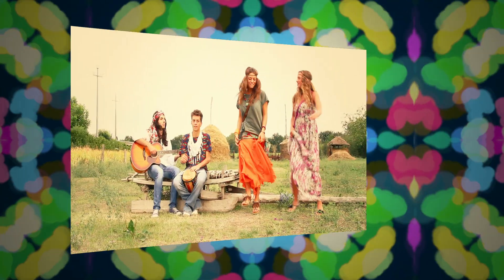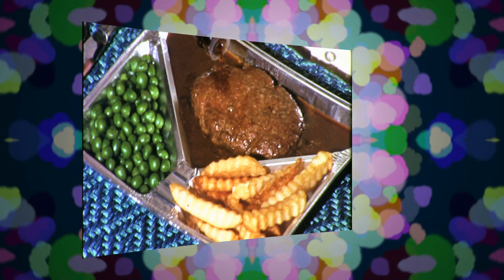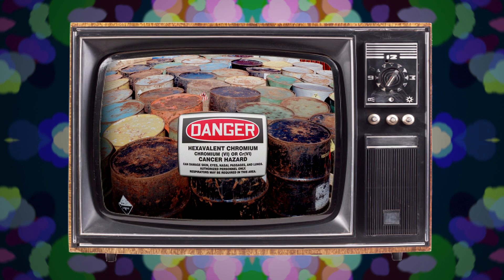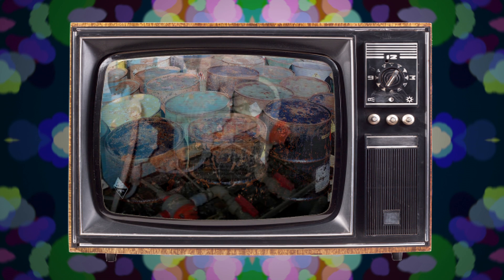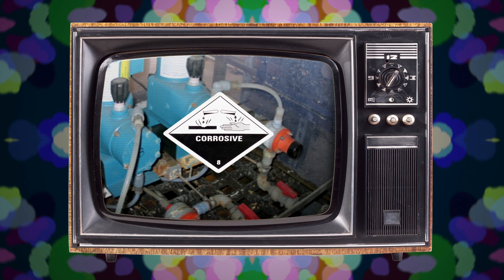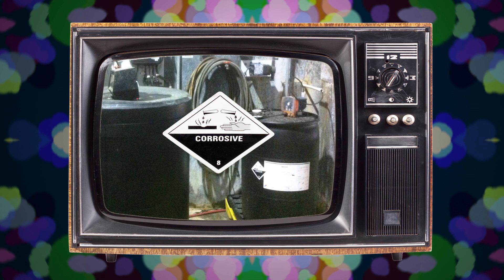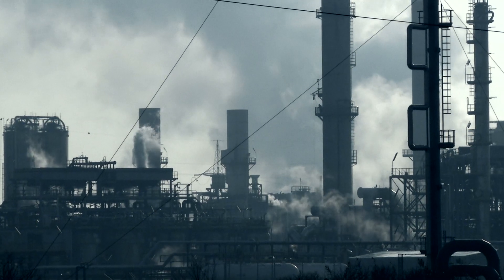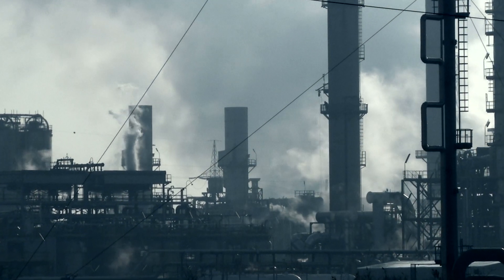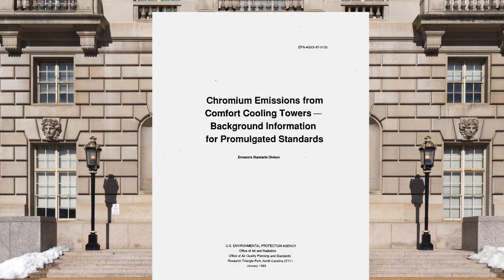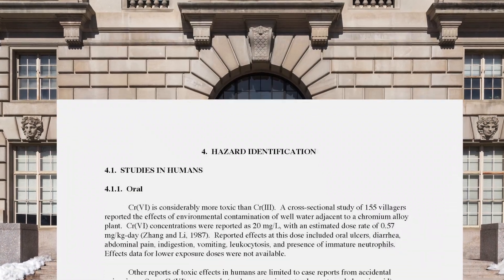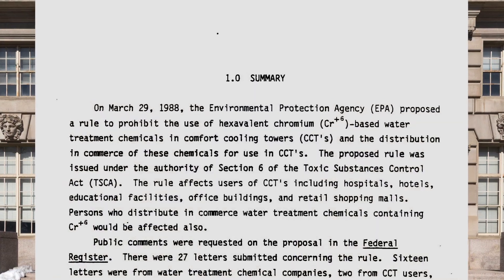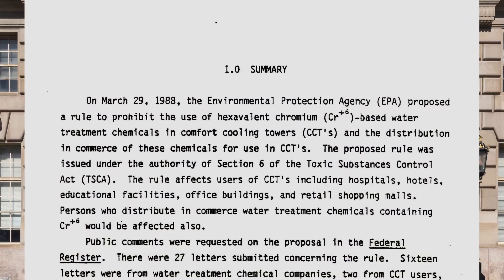Flash back to the era of bell-bottom jeans, the gas crisis, and TV dinners. In those early years, water treatment was based on chromate chemicals, the dominant method for evaporative cooling systems at the time. These chemicals were typically fed in conjunction with acid to maintain pH in a near-neutral range. This treatment approach was very effective at minimizing corrosion and maintaining the galvanized surfaces. However, while effective, chromate-based chemicals were found to have negative environmental and health impacts. Therefore, beginning in the 1970s, the United States Environmental Protection Agency regulated and ultimately prohibited the distribution and commercial use of chromium-based water treatment chemicals in comfort cooling towers.